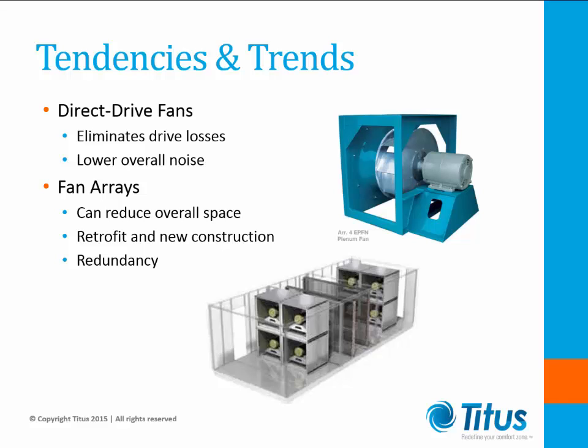Fan arrays are multiple small direct-driven units that are used in lieu of a large fan itself. Applied properly, the fan array can reduce the overall space required for the air handling unit while providing redundancy. Depending on the number of fans, they can be controlled in unison by one or more VFDs. Like so many other things related to air handling units, care must be taken when applying a fan array to ensure the goals of the project are being met as efficiently as possible.